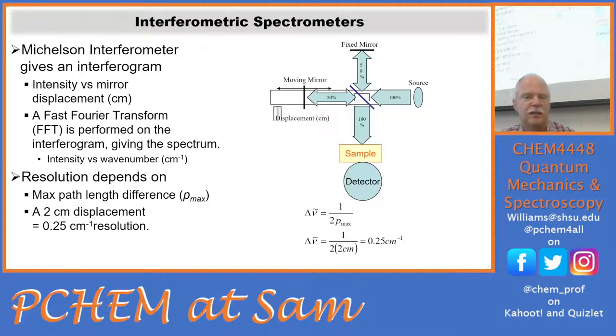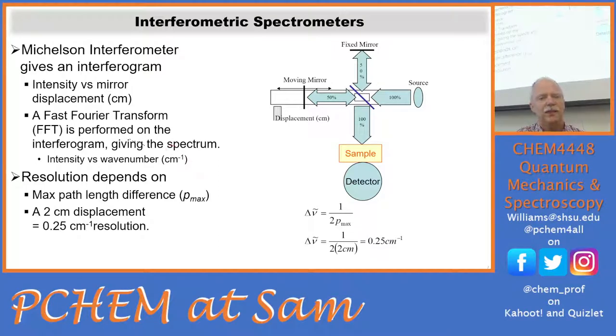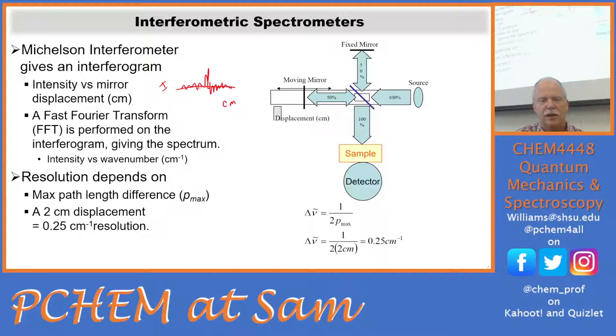Now let's talk about interferometric spectrometers. This is a picture of a Michelson interferometer — the instrument is called the interferometer and the data that comes out is called an interferogram. It measures intensity versus mirror displacement in centimeters. As the moving mirror moves back and forth we see this intensity curve — a really funny-looking shape we'll see in the next slide.